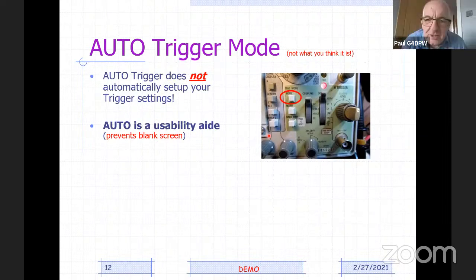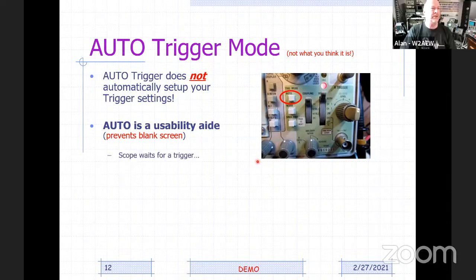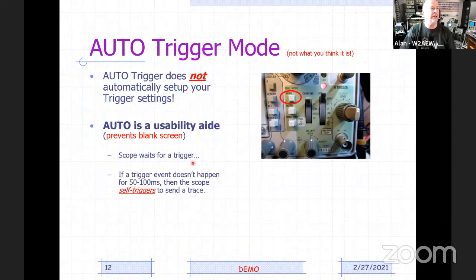I don't know. Okay. Can I just come in on this one? Sure. One easy way of explaining that would be to assume that it's an auto free run. In other words, the signal will just free run across the screen. And I think that's probably an easy way to explain it. That's exactly right. So what happens with auto, exactly as you described, is the scope waits for a trigger. If it doesn't get a trigger within about 50 to 100 milliseconds, then it self triggers. It just says, okay, I'm going to issue a trigger anyway. So that's a free run type mode, saying, okay, the trigger you told me to use doesn't exist, so I'm just going to free run here. But if while I'm free running, you get the trigger adjustment right, then I'll lock on your signal.